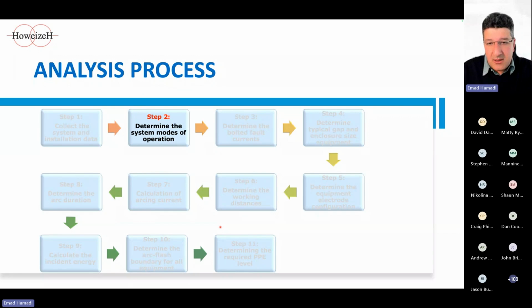The next step, which is also crucial, is to determine the system mode of operation. A very important step is understanding the different modes of operation of the electrical system. Each mode can significantly impact the short circuit level, which in turn affects the incident energy calculation. To determine the system modes of operation, we must identify the scenarios that provide both the maximum and the minimum available short circuit, which requires a thorough understanding of the control philosophy and the possible switching sequences. In complex systems, there are many modes of operation that all need to be considered.